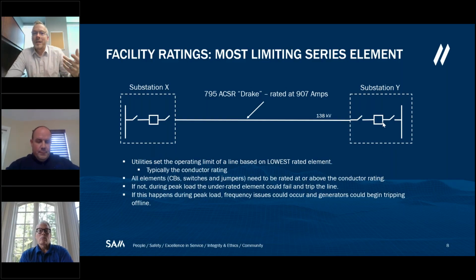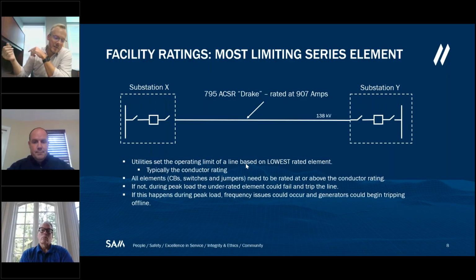If you have an underrated jumper, let's say a jumper between substation X that ties the last switch to the bus section, and that jumper is rated at 750 amps, and the utility pushes 900 amps across that facility, the jumper gets hot and burns up and disconnects, and that entire transmission line trips offline. Now let's say there's a generation facility connected to substation Y. That generation facility could be removed from the grid, and that's where bad things occur in terms of frequency and the potential for blackouts. So it's a very important NERC compliance standard that transmission operators need to adhere to.